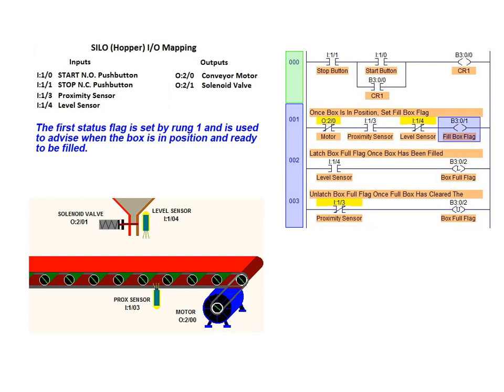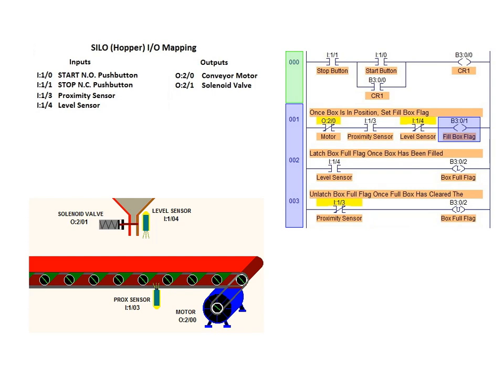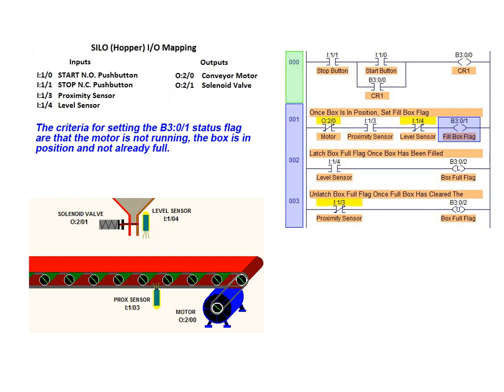The first status flag is set on rung 1 and is used to advise when the box is in position and ready to be filled. We will use the bit file address B3 0.1 for this status flag. The setting of this status flag is dependent upon three conditions: first, the motor cannot be running; second, the proximity sensor must detect a container at the fill station; and lastly, the level sensor must not be tripped, indicating that the box has not already been filled.